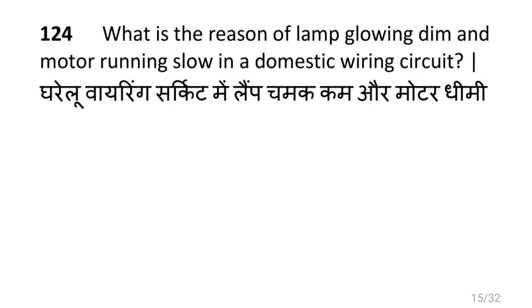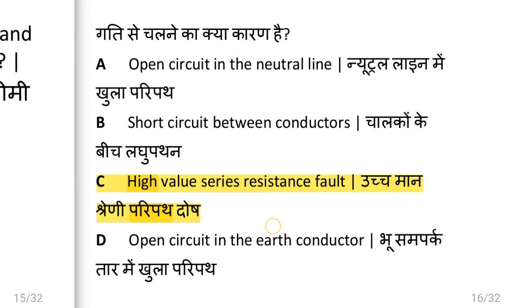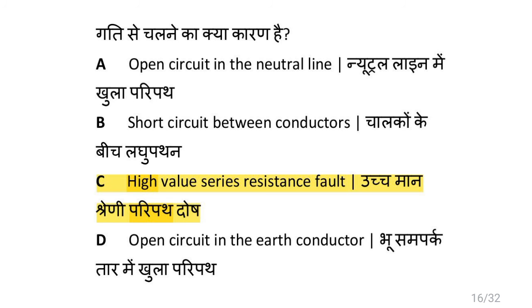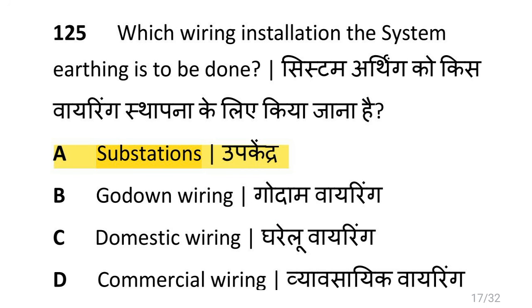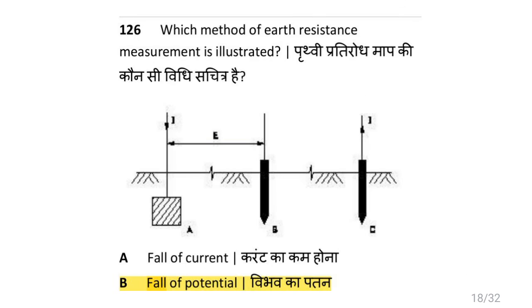What is the reason for a lamp glowing dim and motor running slow in a domestic wiring circuit? High value series resistance fault. Which wiring installation requires system earthing? That is substation. Which method of earth resistance measurement is illustrated? That is the fall of potential method.